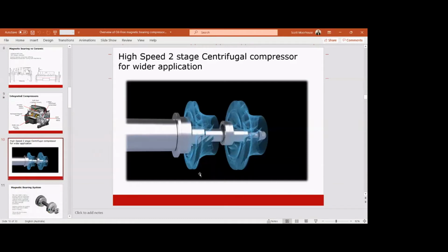So on a centrifugal compressor, we have a number of different operating conditions when we're using a centrifugal compressor. And in the past, centrifugal compressors have mainly been used, 95%, 98% of the time, for water-cooled applications, because the pressure ratio could not be high enough to use them for air-cooled applications. To get higher pressure ratios, we either need more impellers, so more stages of compression, or we have to have higher speed. And so with the oil-free magnetic bearing technology in the market today, we have 2 impellers and very, very high speed.